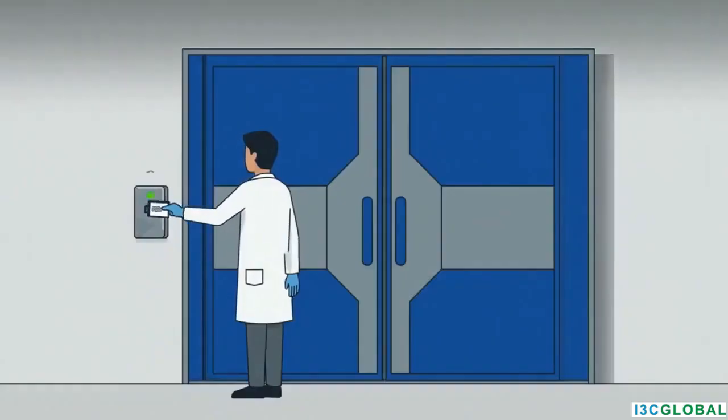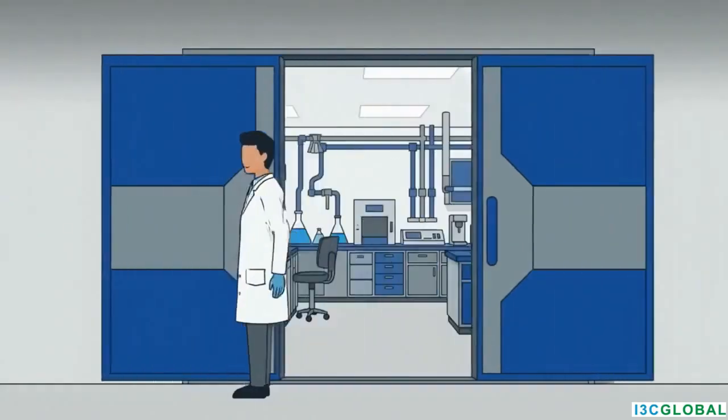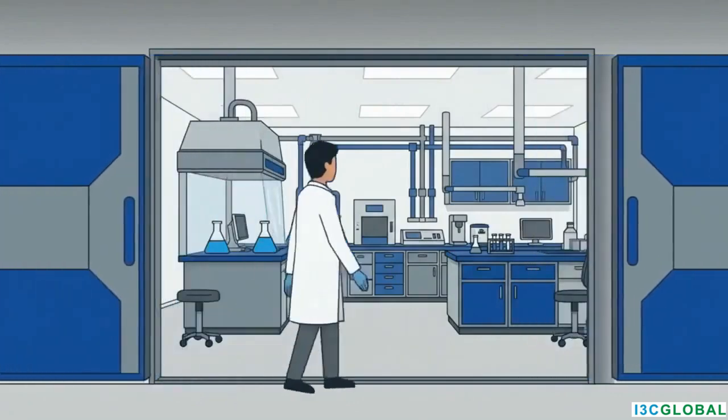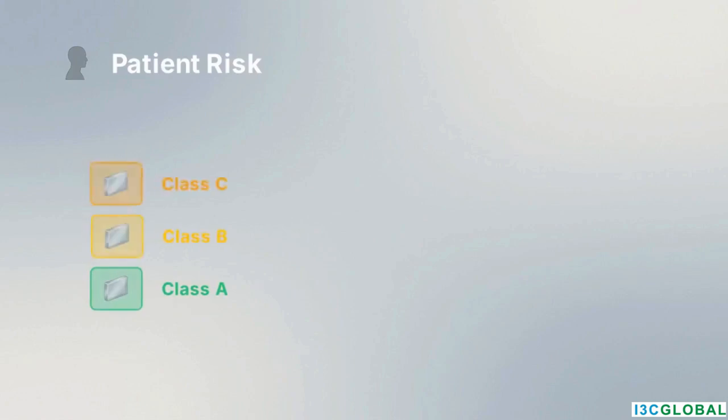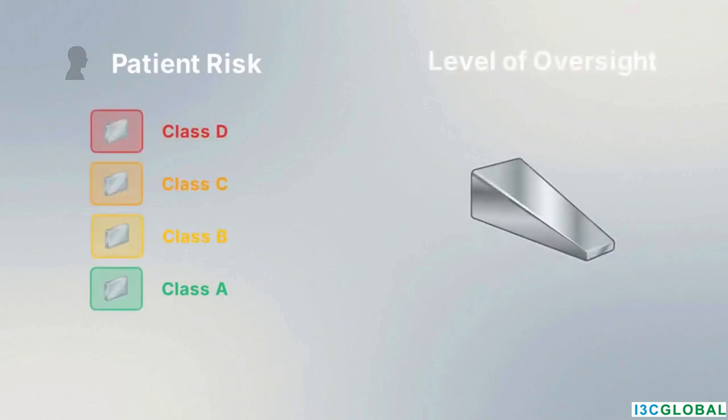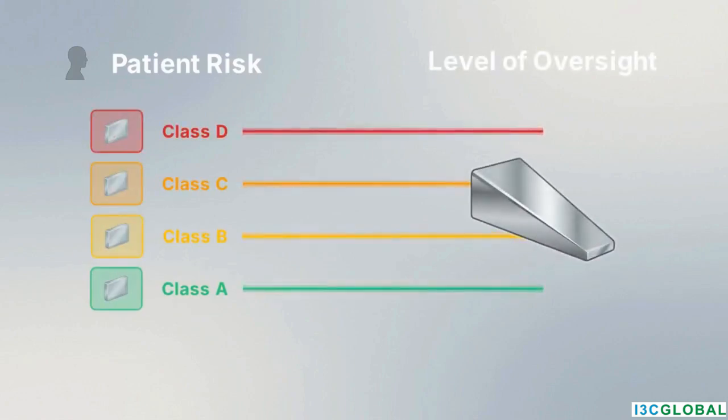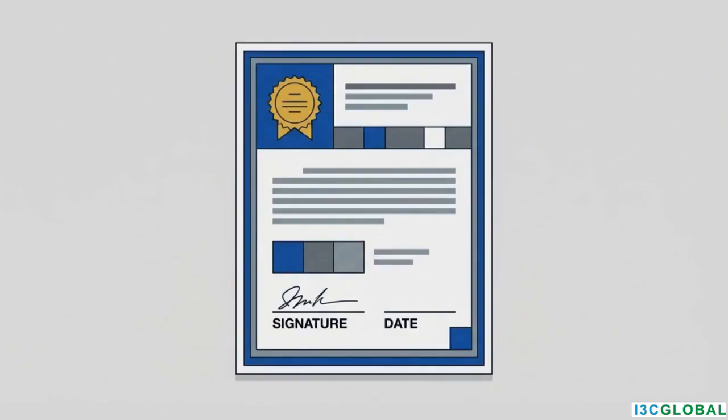Europe maintains a high barrier to entry for medical diagnostic devices. Securing approval for an in vitro diagnostic, or IVD, requires a risk-based assessment, where the level of oversight is determined by the potential impact on patient safety. The final requirement for every manufacturer is the EU Declaration of Conformity.